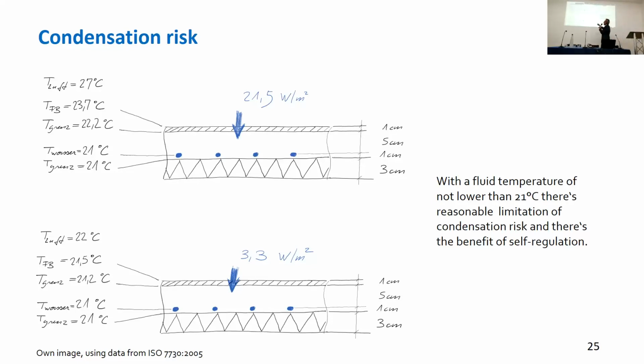And I like this operation with only 21 degrees very much, because it shuts off if the room gets cold. So I like the idea not to control like hell in the mechanical system, but to have a self-controlling system. If this temperature stays at 21 the whole summer long and the room gets down to 22, the cooling stops automatically just because of temperature differences. And this is how we operate our cooling systems. We run them for the whole summer at 21 degrees, and they just shift temperatures and they stop cooling if not needed.